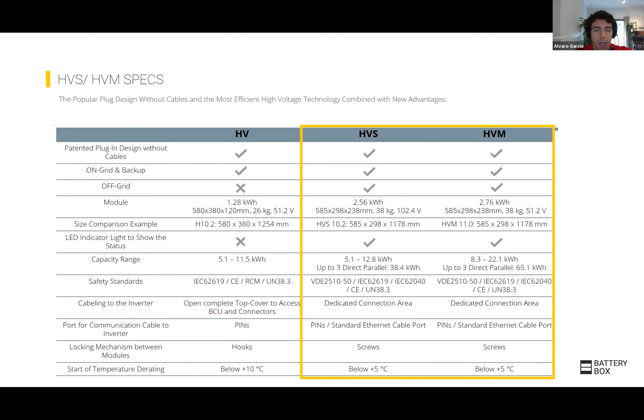So how to choose between the HVS and HVM? As mentioned in the first slide, the number of batteries tells you the voltage of the system: two batteries give you 204 volts, three batteries 306, and so on. You need to multiply that by the inverter current — in this example, I've used an inverter current of 25 amps.